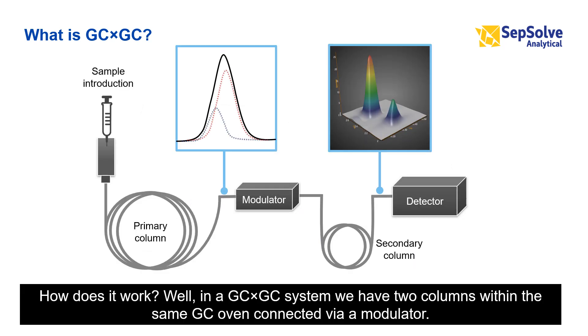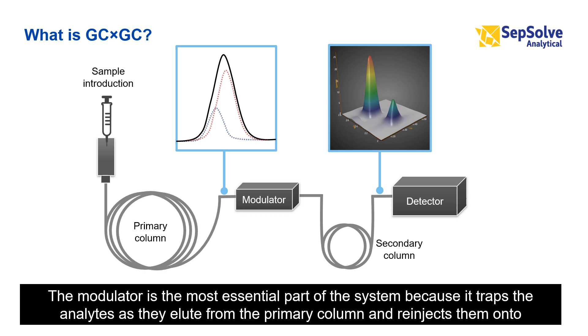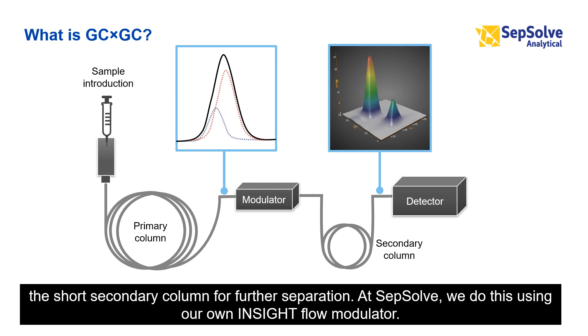How does it work? In a GC×GC system, we have two columns within the same GC oven, connected via a modulator. The modulator is the most essential part of the system, because it traps the analytes as they elute from the primary column and re-injects them onto the short secondary column for further separation.